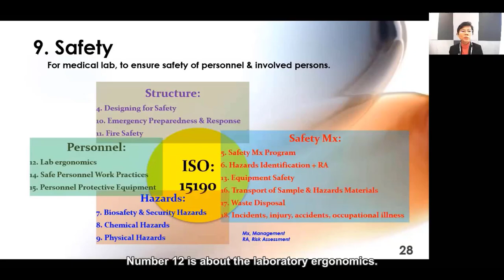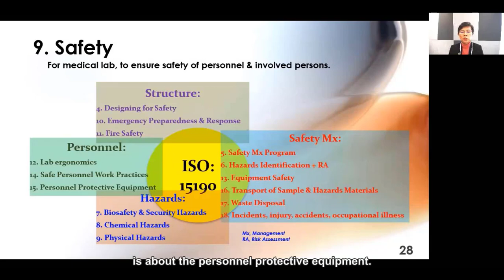For the personnel, you are going to involve requirement number 12 about laboratory ergonomics. Number 14 is about safe personnel and work practice. And number 15 is about personal protective equipment. So let's go a bit deeper into the issues to be concerned about in 15190. I just pick some important points for you, such as when a laboratory is constructed, an appropriate building code containing architectural safety standards for laboratories shall be followed. Ensure that containment of microbiological, chemical, radiological, and physical hazards is appropriate to the level of the work area.